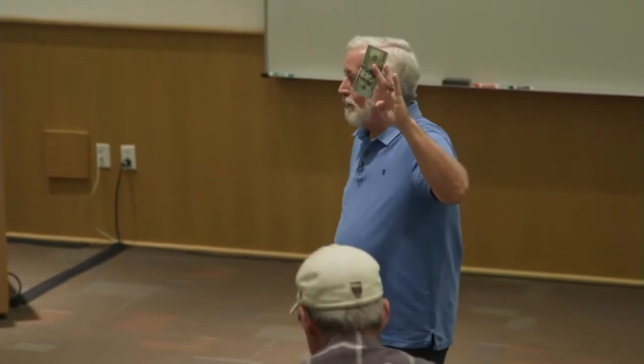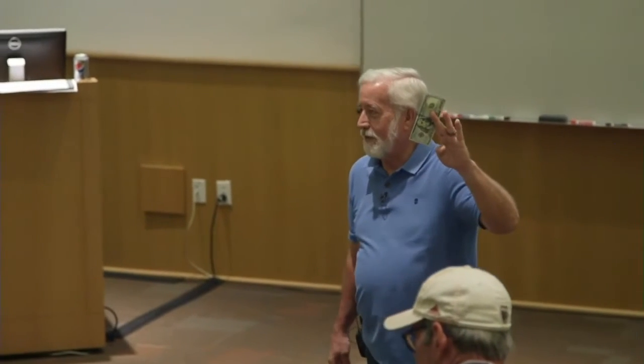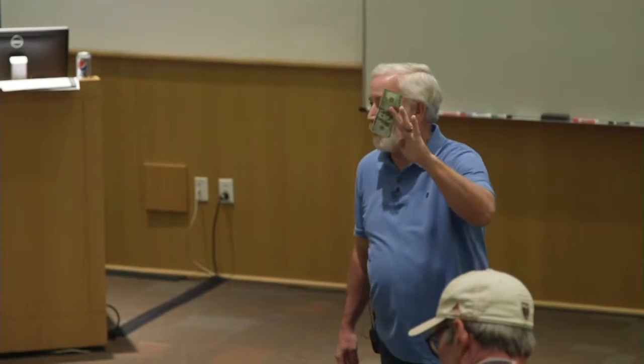Anybody want to do that? Seeing the $100 bill really drives it home, doesn't it? Would you want to take this and drop it down the toilet and flush it? Well, that's what we're doing when we're sticking ducts in hot attics and we're not burying them in insulation and we're not insulating them even a little bit better. R8 insulation, is that very much? We have no R8 requirement anywhere in a wall or a ceiling or anything, but yet we're using R8 when we have the greatest temperature difference.